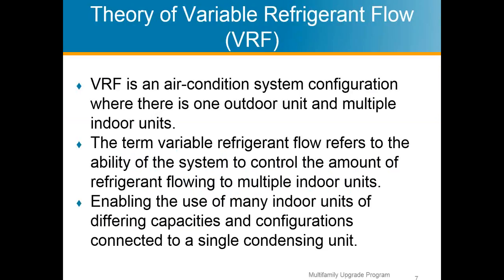So just want to talk briefly about the theory behind the VRF system. It's an air conditioning system configuration where there is one outdoor unit that serves multiple indoor units. So in your conventional split system, you would have one outdoor unit dedicated to one indoor unit. With the use of variable refrigerant, we're able to use multiple indoor units with one outdoor unit. So the term variable refrigerant flow refers to the ability of the system to control the amount of refrigerant flowing into multiple indoor units, enabling the use of many indoor units in differing capacities and configurations connecting to a single condensing unit.